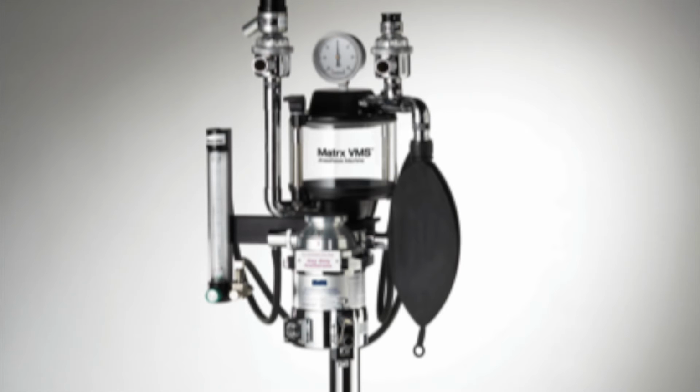The flow into the scavenger system is dictated by the pop-off valve in the rebreathing system and the valves in the reservoir bag in the non-rebreathing system. Our scavenger system at Pierce has the F-air canister, which is an activated charcoal canister, and is replaced after 8 to 12 hours of use or if there has been a weight gain of 50 grams.